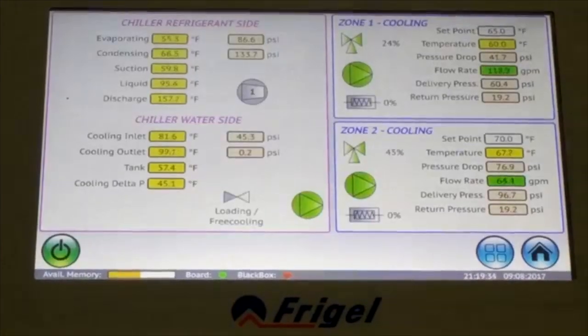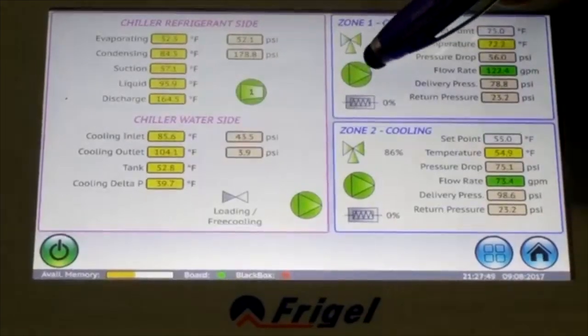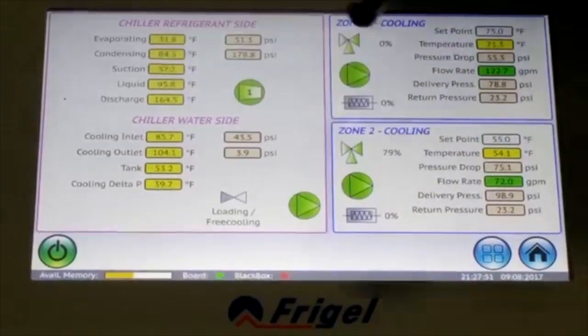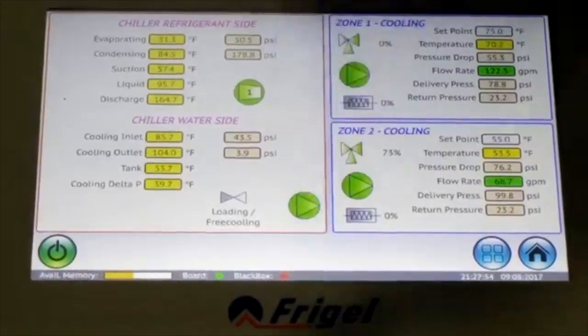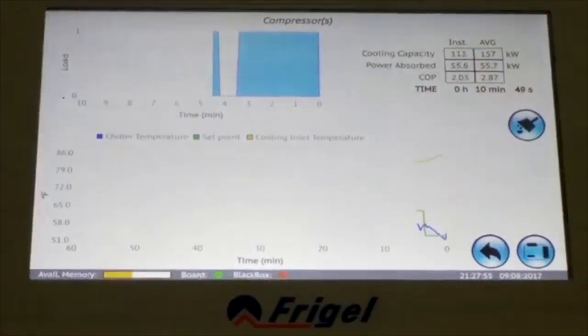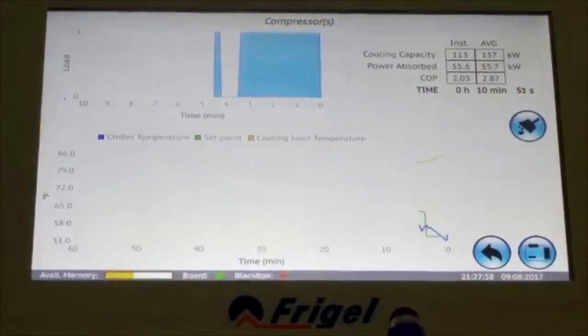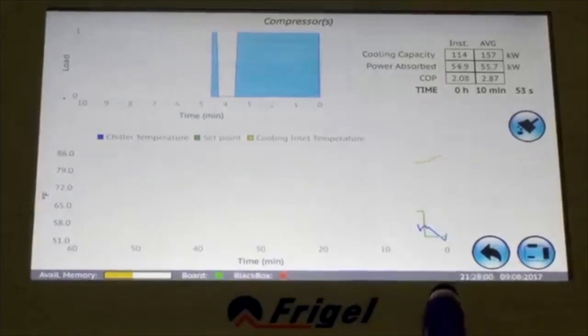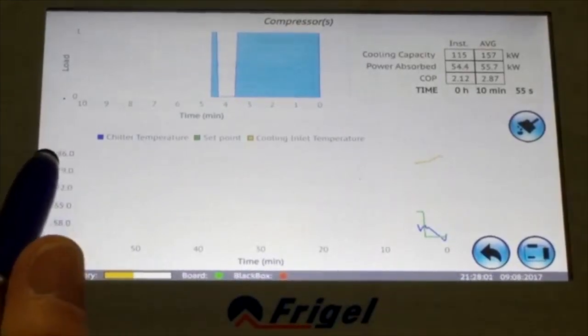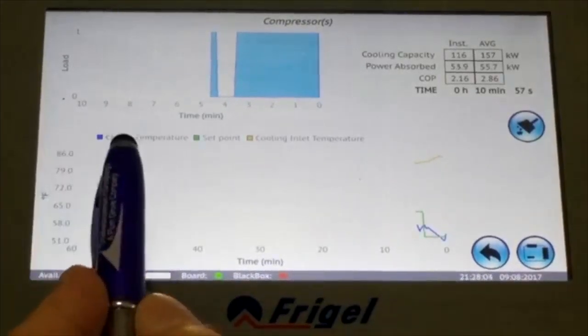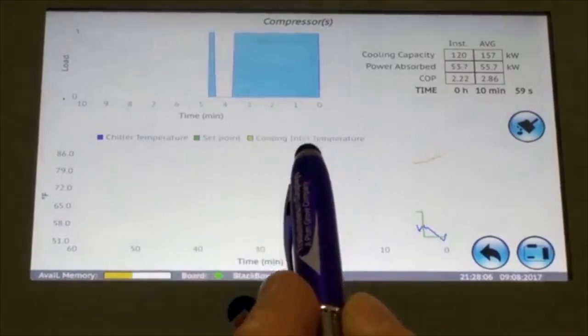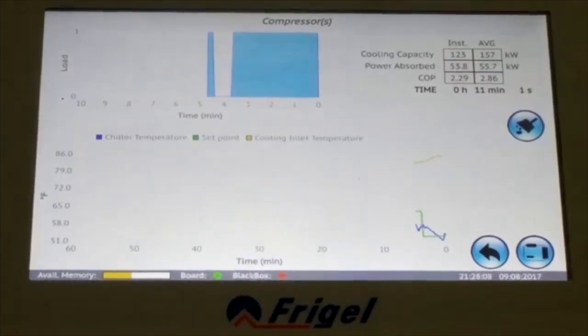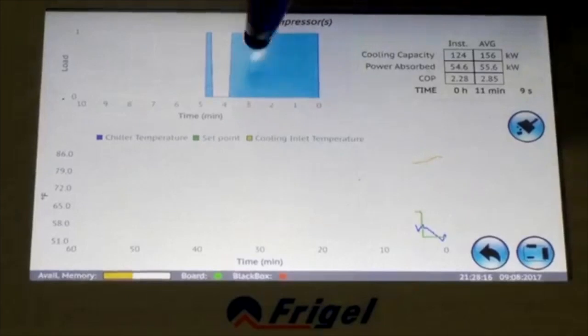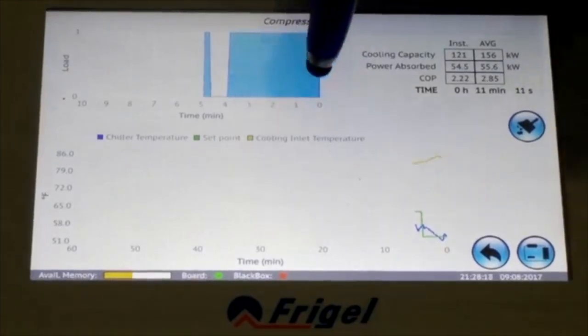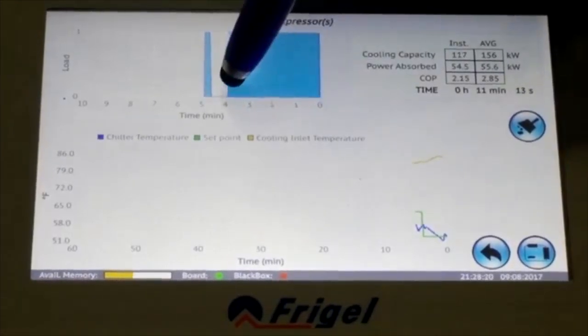In the same manner as the temperature control zones, touch the green arrow in the chilled water section and all parameters of the refrigeration system are displayed. In the bottom graph, supply temperature, set point, and inlet EcoDry temperature to the condenser are displayed. Up top, the compressor operation is displayed, as well as coefficient of performance, cooling capacity, and kW.